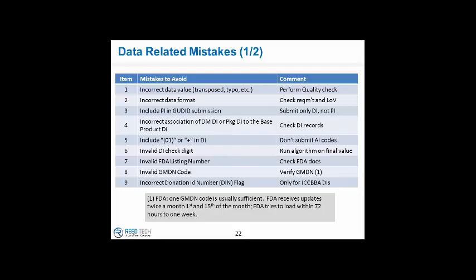But I think what she was referring to is that every base product needs to have a submission, an individual record. You might have 10,000 items that you market. Each of those 10,000 medical devices would need to have a UDI and be recorded with the FDA.